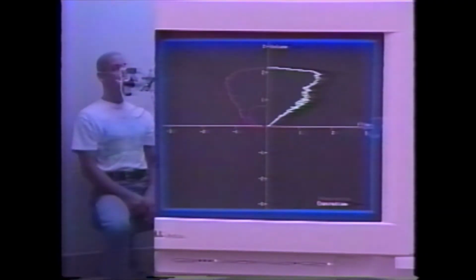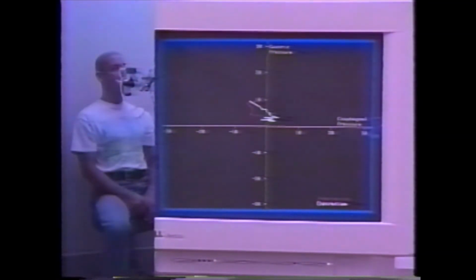For each breath, the system detects the start and end of inspiratory flow, which makes it possible to calculate the parameters which are relevant for the analysis of respiratory mechanics online. Here, for example, is a breath-by-breath display of flow volume curves. Inspiration is plotted in red and expiration in yellow. Here is an example of a Macklem diagram, with esophageal pressure plotted on the x-axis and gastric pressure plotted on the y-axis. Again, inspiration is plotted in red and expiration in yellow.